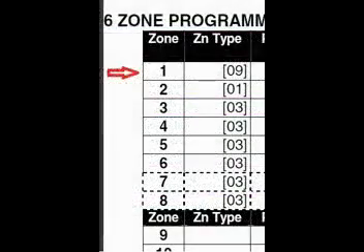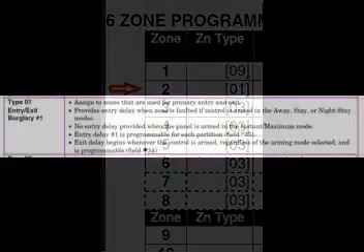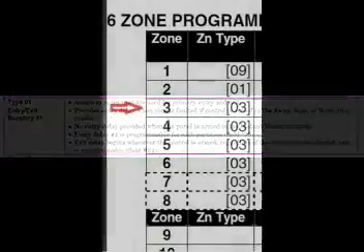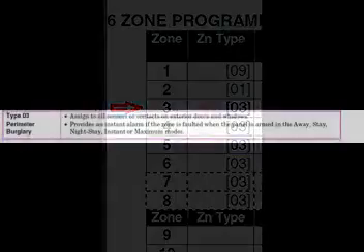Zone type 9 is a supervised fire loop. Supervised means it has to have an end-of-line resistor, and it's currently looking for heat or smoke detectors. Zone 2's default is zone type 1, which is used for the door you use for entering and exiting the house — it has its own zone type because you want to be able to assign entry and exit delays to this zone. The default value for the remaining zones, 3 through 8, will be zone type 3, which correlates to your perimeter — things like window reed switches and glass breakage detectors.